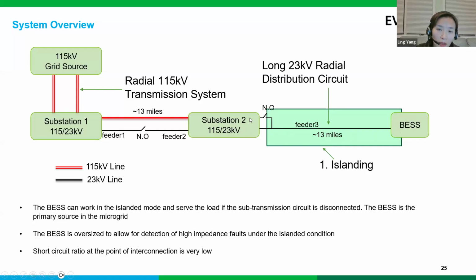And not only that, the source station is connected through just one 115 kV transmission line. So overall, the substation is also radially fed by the transmission system. So overall, the system stiffness is relatively weak in that area. And the distribution feeder that the battery interconnects to is about 13 miles. We have quite a lot of load at the end of the circuit. At the end of the circuit, it takes up about 50% of the overall circuit loading on the system peak load day.